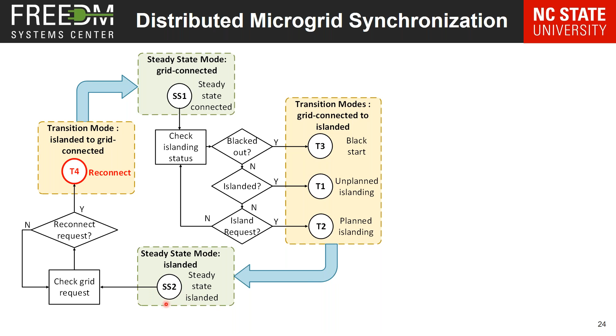This again is fairly difficult. Most strategies rely on a large distributed generation source, typically a diesel genset. When I say large, it can be megawatts, to be able to provide that frequency. Then all you have to do is match that one device, adjust the frequency of that device to match what's coming on the grid. Once those are in sync, you should be able to retransfer. There's a lot of other pieces that go before that—you want to do a lot of checks, but that's the process.